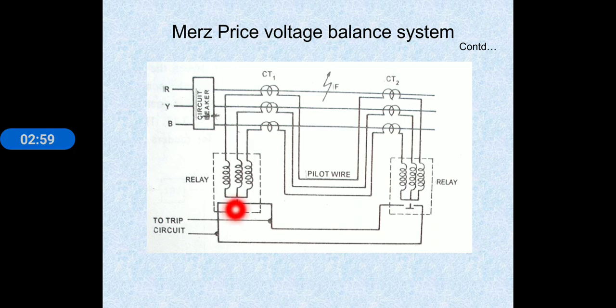Under normal conditions, the current entering this line is equal to the current leaving at the other end. At that time, the voltages of the secondaries are equal. Both the entering and leaving currents are equal, and both secondaries of the current transformers maintain the same voltage in normal conditions. This is what is called a balanced voltage system.